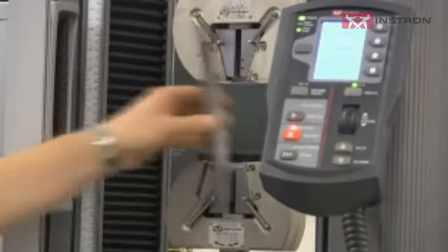What we're going to do here is use a rigid material. In this case, it's just a piece of steel. So we know it's straight and flat. We load it into our grips, and I've got a test set up to run it up to 500 pounds.